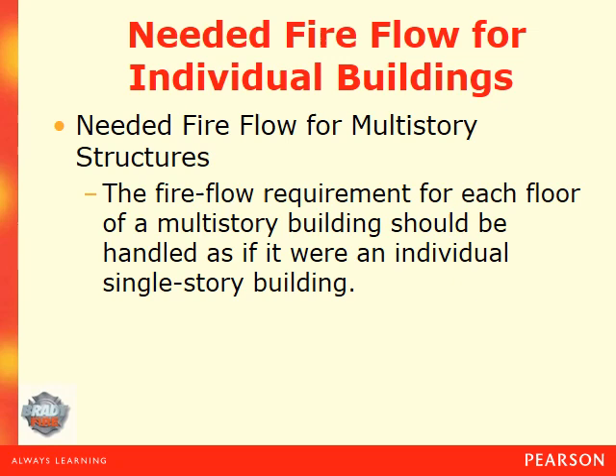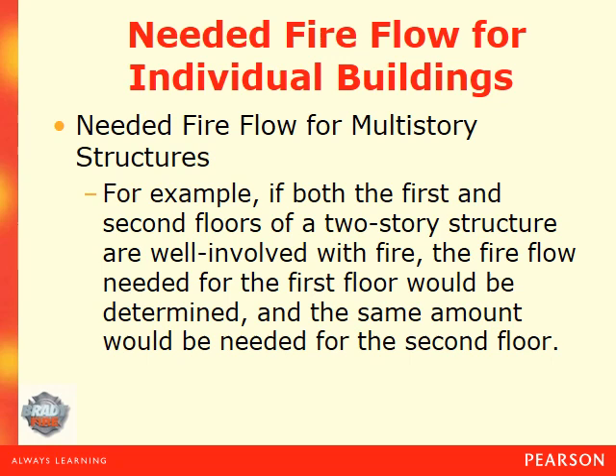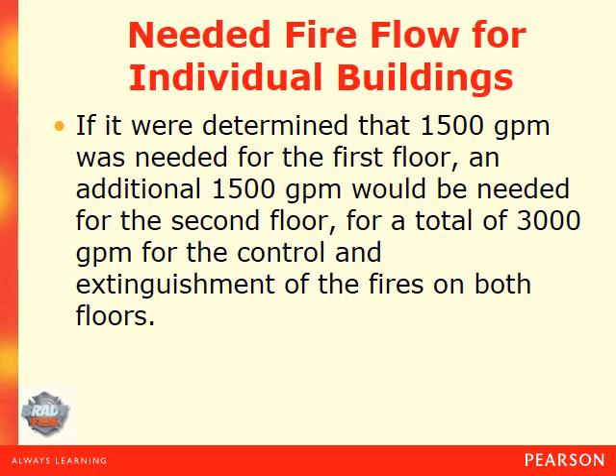The fire flow required for each floor of a multi-story building should be handled as if it were an individual single-story building. For example, if both the first and second floor of a two-story structure are well involved with fire, the fire flow needed for the first floor would be determined, and the same amount would be needed for the second floor. If 1,500 gallons per minute was needed for the first floor, an additional 1,500 gallons per minute would be needed for the second floor, for a total of 3,000 gallons per minute to adequately control the fires on both floors.